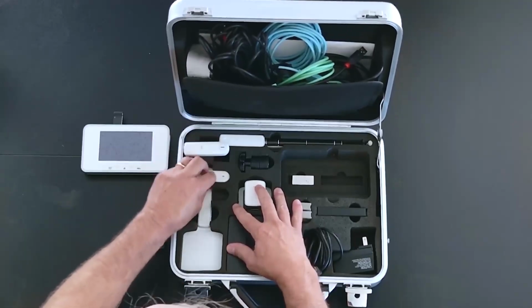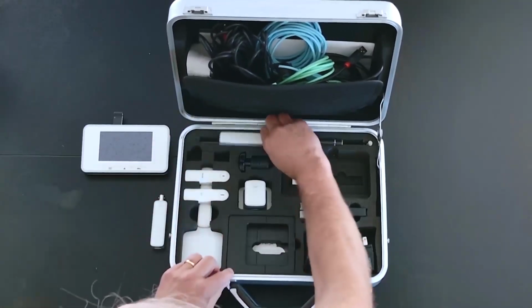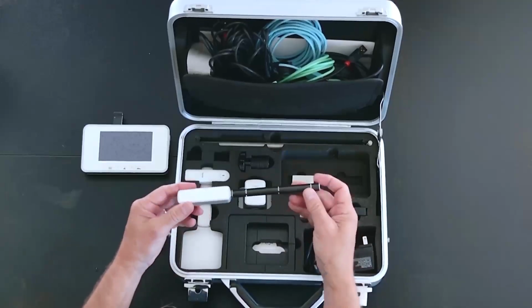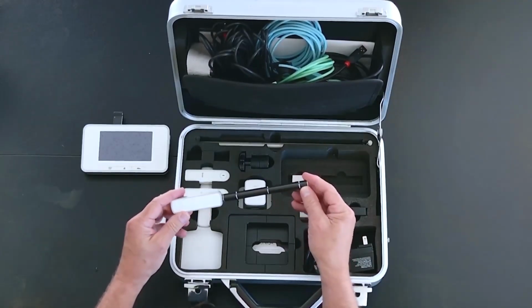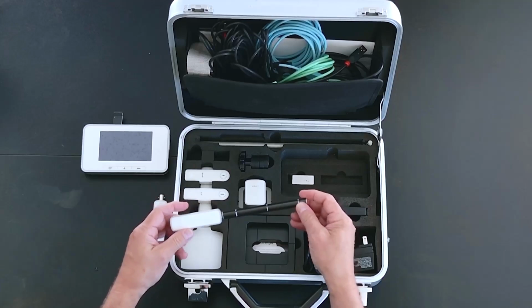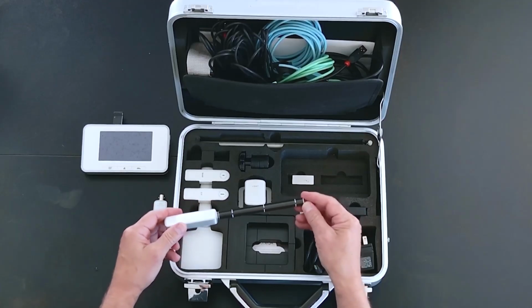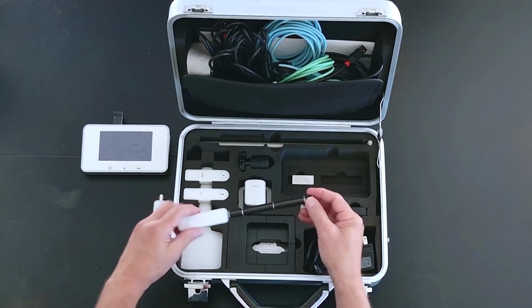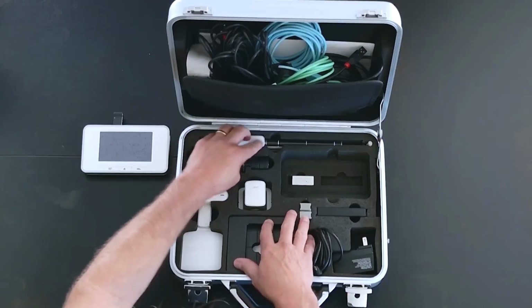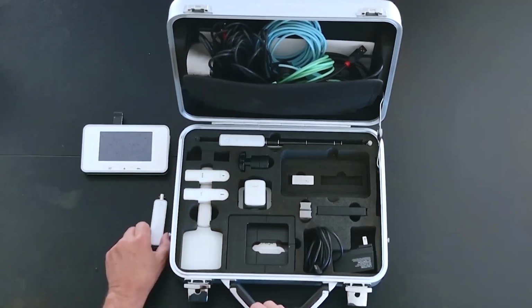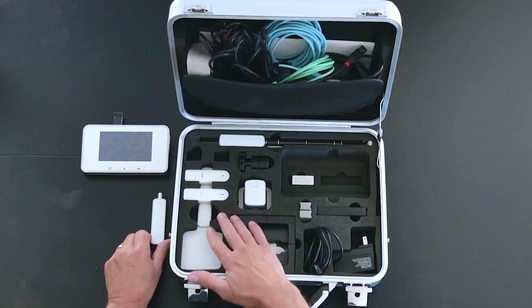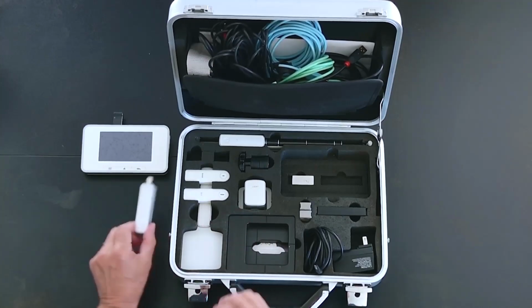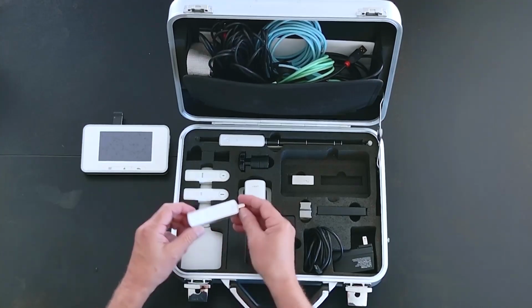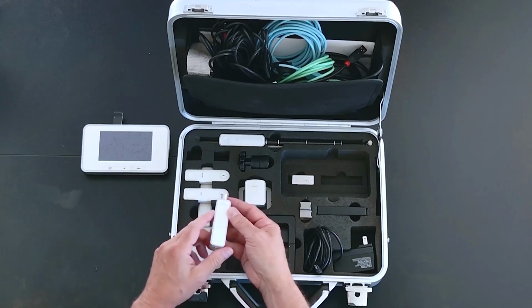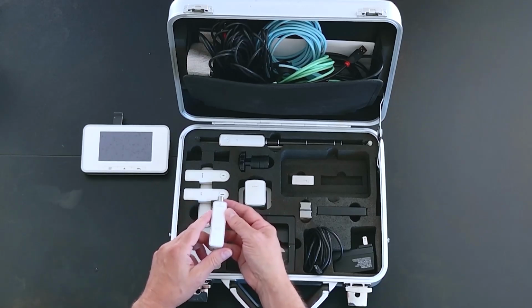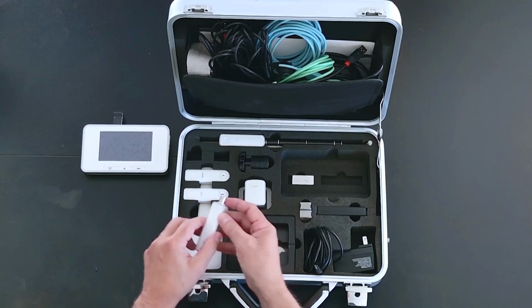Put these back. And the CT sensor is actually an ion chamber, and it is used to measure dose in a CTDI phantom, which will come up in one of our subsequent episodes of these demos. And last but not least, this one is an older case. It doesn't have a slot for the volt sensor, but we also have the volt sensor, which was used to measure voltage, of course. It can be used with a Prova 15 current clamp to measure mA non-invasively.